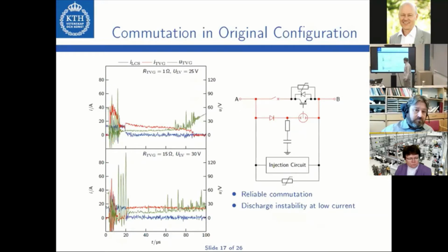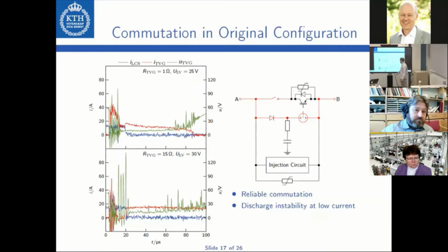The thing is, though, that there is the chance of a discharge instability. The green curve, which is depicted in these graphs, corresponds to the measured voltage across the triggered vacuum gap. As you can see, at this low current level, the discharge voltage is relatively volatile for both resistor values. But in case of the lower resistor, there is a discharge instability, which leads the discharge to extinguish. The DC circuit breaker interrupts at this point. However, it was not supposed to interrupt, so this is undesirable. We think that this happens because the discharge in the triggered vacuum gap starts interacting with the RC circuit, but only if the resistor value is relatively low. By carefully dimensioning the RC circuit, the instability can be avoided, as you can see for the higher resistor value. If the current level is increased, the instability completely disappears, since also the volatility of the discharge reduces.